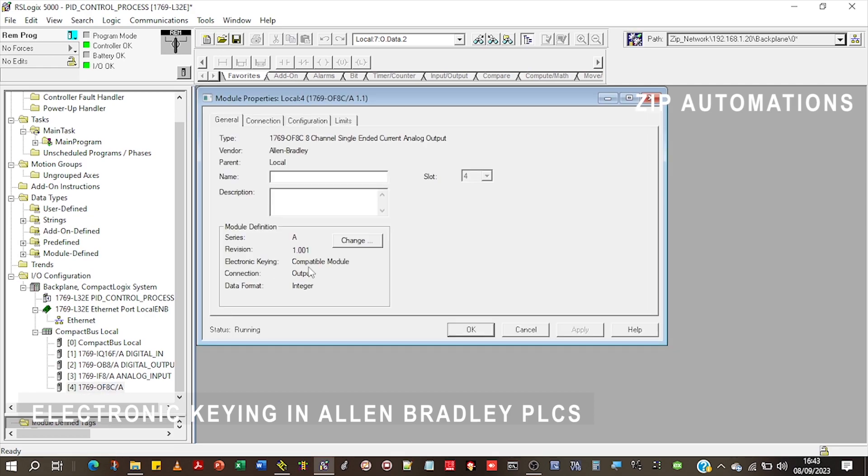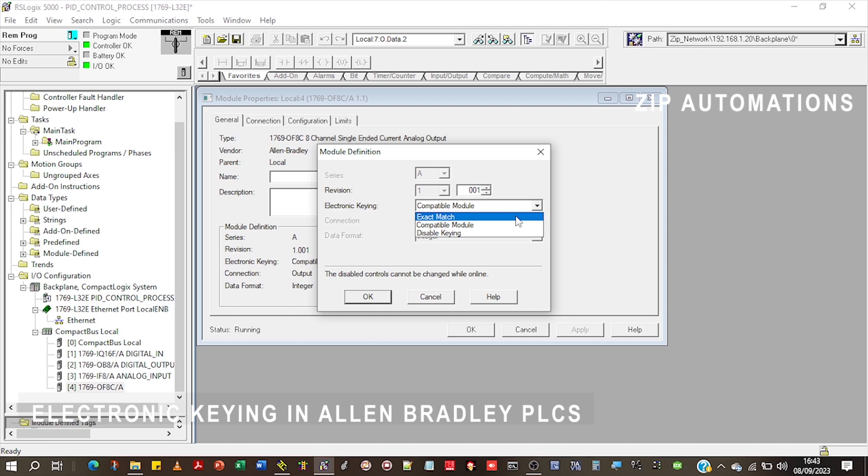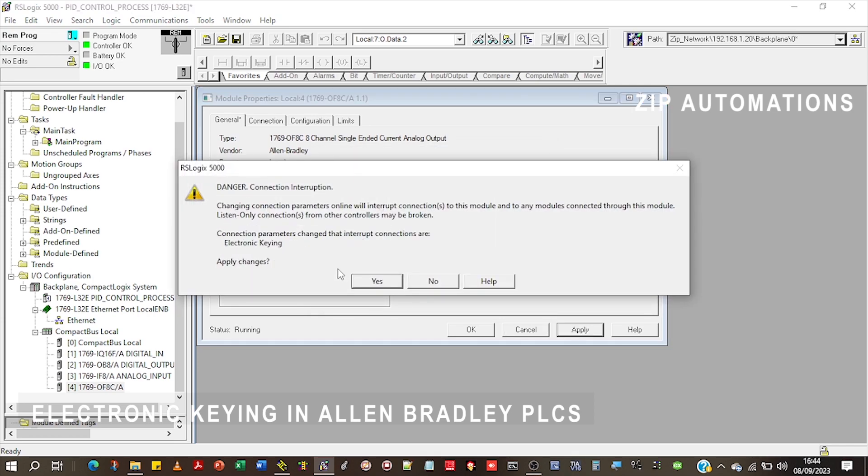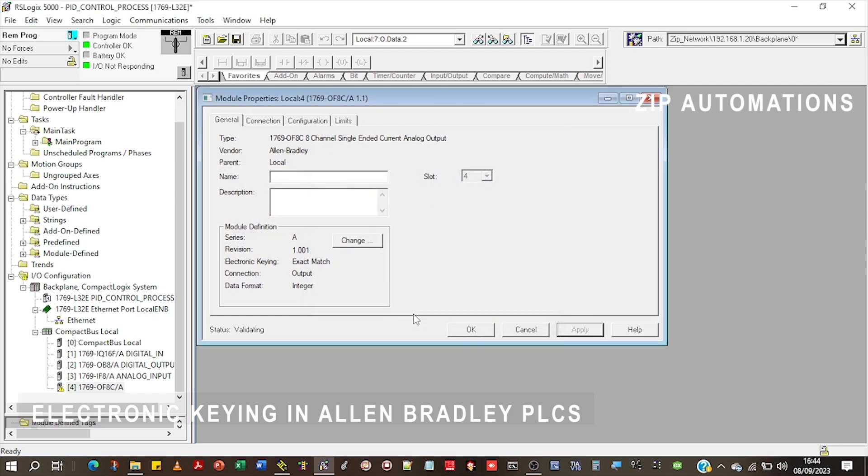But if I select exact match, it means that the major and the minor revision would matter. If I do that and I click OK, then you can see that the fault has appeared again because what I configured here is not an exact match.